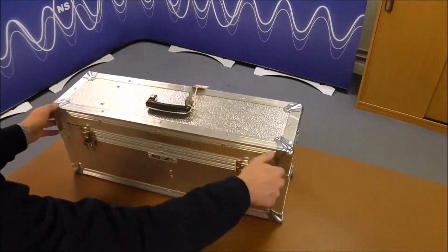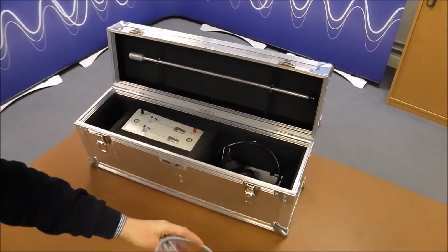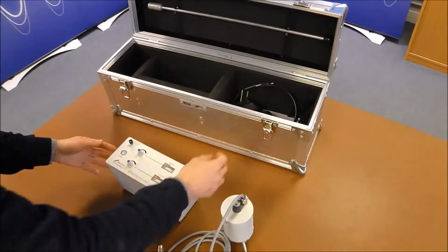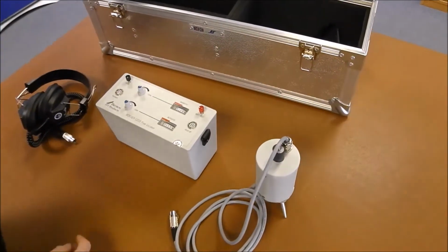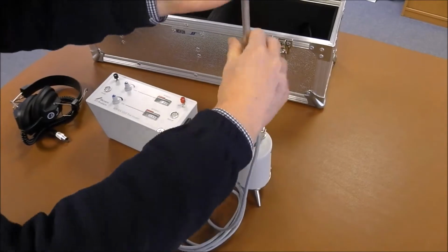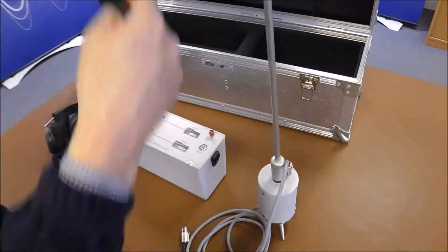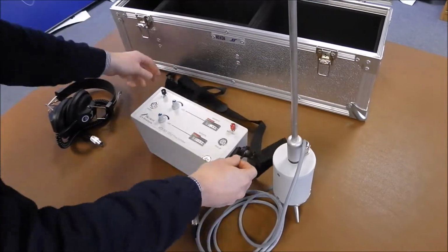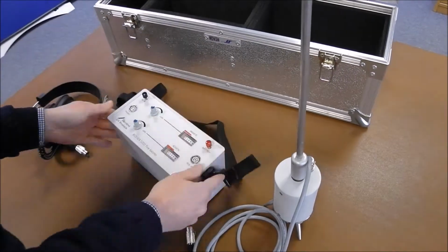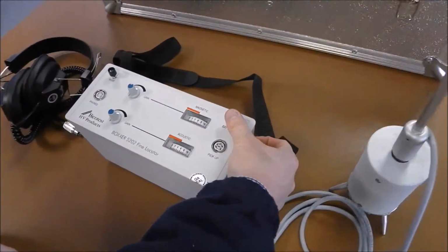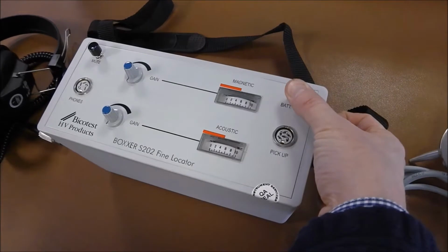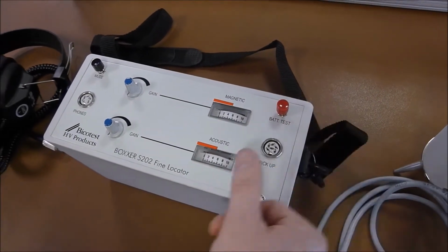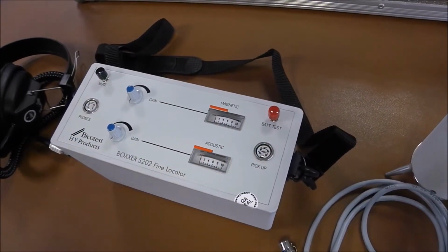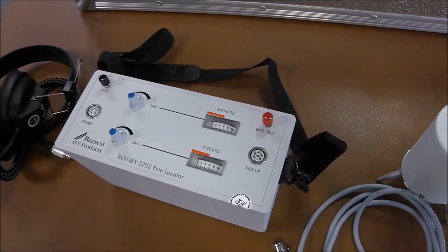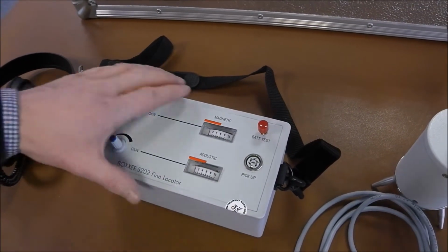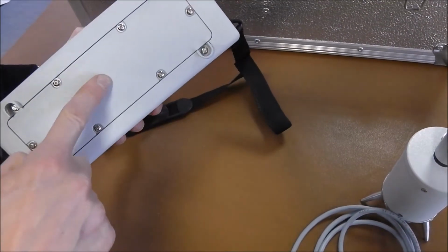And onto the operation of the unit. Remove the acoustic transducer, amplifier unit and headphones from the carry case. Install the extension handle to the acoustic transducer and attach the neck strap to the amplifier unit. Instrument check. Check the battery condition for each amplifier. Depress the battery test push button switch and check that the deflection on each meter is above 5 on the meter scale. If either meter gives a reading below 5, then replace the appropriate battery.